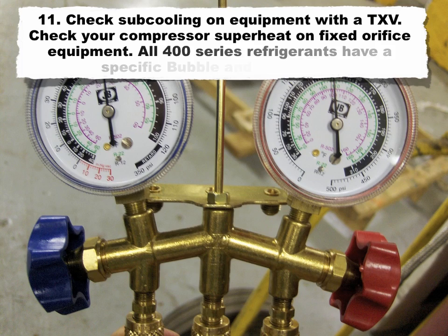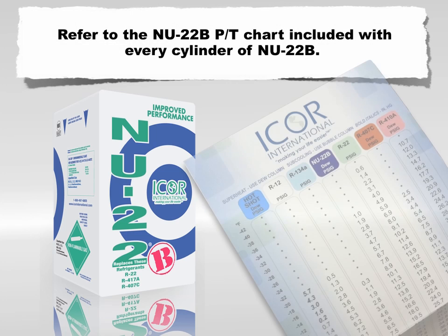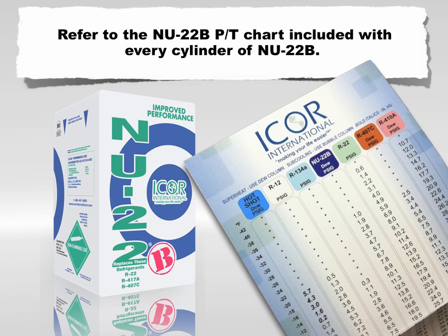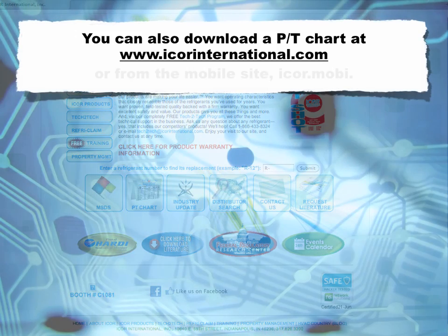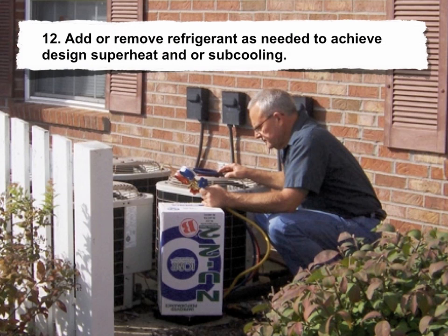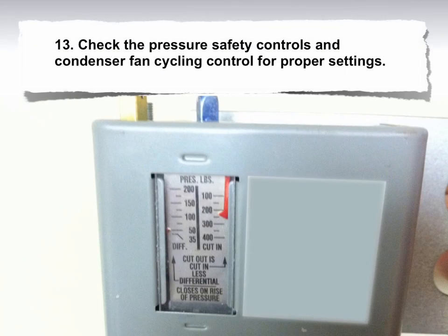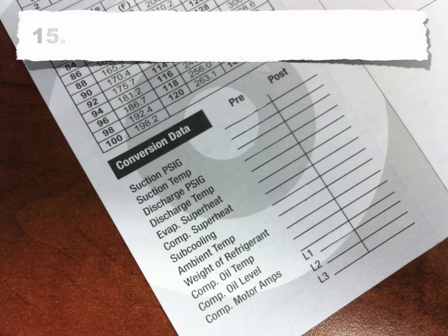11. Check subcooling on equipment with a TXV; check compressor superheat on fixed orifice equipment. All 400 series refrigerants have a specific bubble and dew point — refer to the NU-22B PT chart included with every cylinder of NU-22B. You can download a PT chart at www.icorinternational.com. 12. Add or remove refrigerant as needed to achieve designed superheat and/or subcooling. 13. Check the pressure safety controls and condenser fan cycling control for proper setting. 14. Properly label the equipment with the new refrigerant designation and the amount of refrigerant charge. 15. Record post-conversion data.